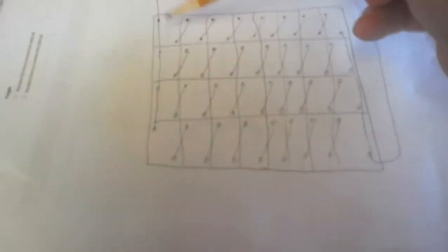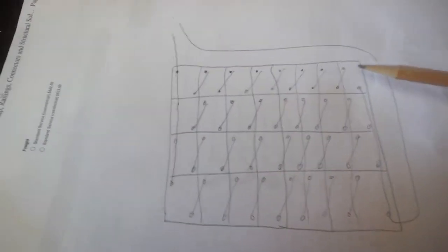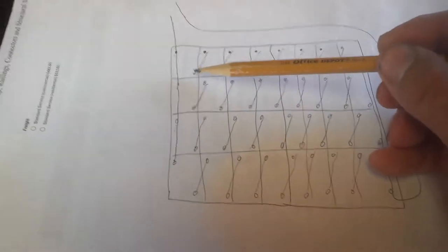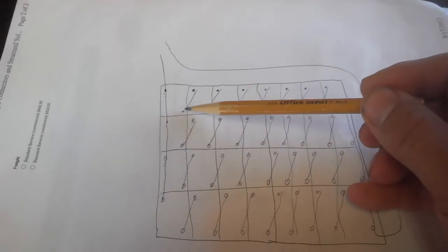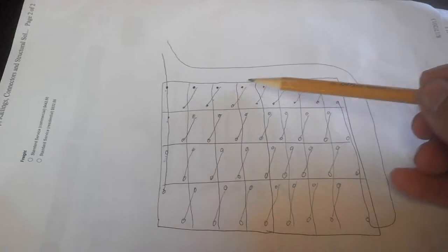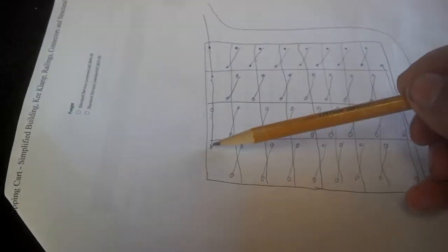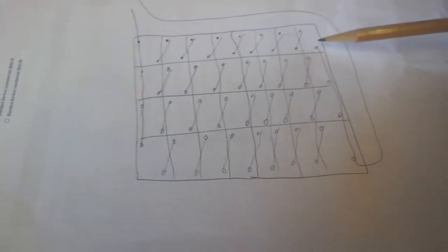But basically, we're going to have 4 rows of 8 batteries connected in series. So we'll be making jumpers, instead of buying them, with 2-aught cable and tinned ends, jumping across positive, negative, all the way across here, and doing that across each one. Then all the positive lined up here coming out this way, and all the negative coming out this way. And so that's how the battery bank is. That's plan A for putting the battery bank together. So that's about it. That's what we're hoping to do.